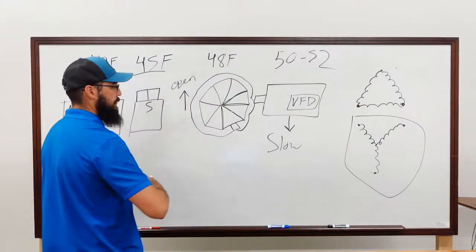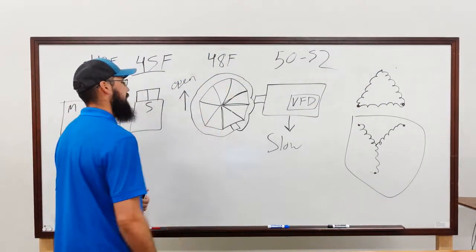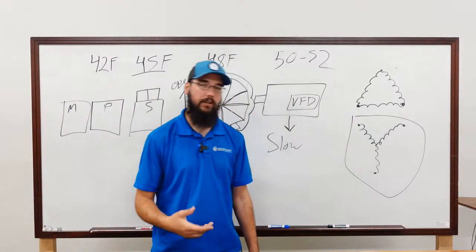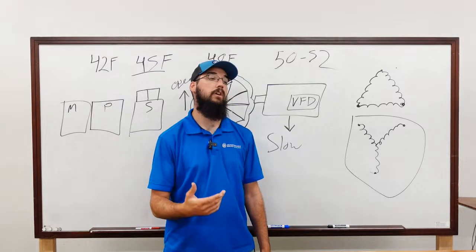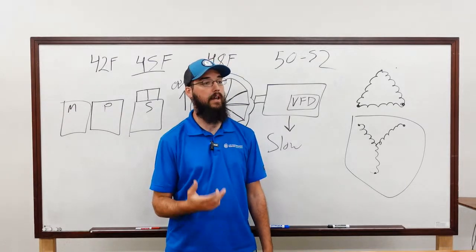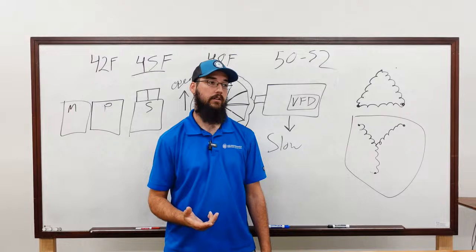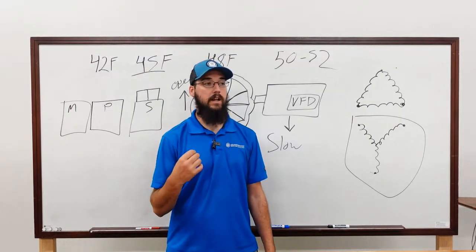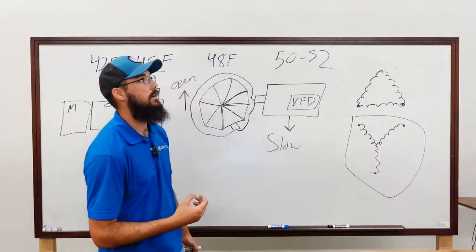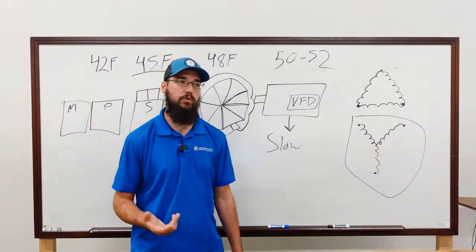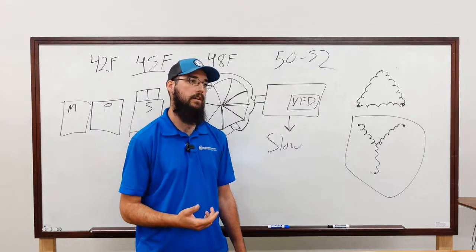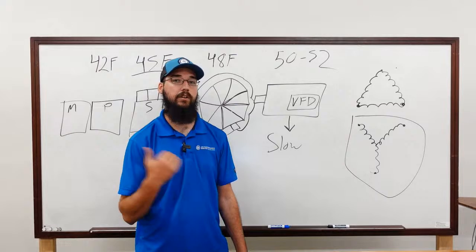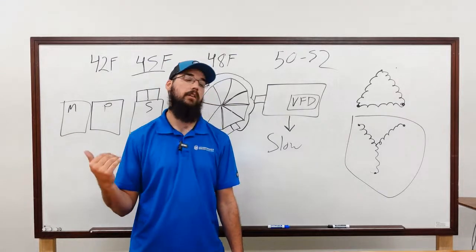Anyway, all of these parameters still apply when it comes to the IGV. It doesn't matter if it's a screw machine either; it's going to apply the same theory. That screw compressor should start at a fully unloaded state. You want it to crank up at minimum. It'll still overcurrent. If a screw compressor tries to start with any kind of load on it, the parameters inside of that compressor or the control system are going to see that and cut it off, because it says, hey, something ain't right here.